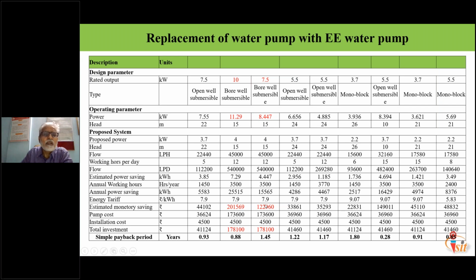For the proposed power, we did a computer simulation using available software with Grundfos. For this particular application, considering the head and discharge, a 4 kilowatt pump is suitable. Head is 15 meters, and the required flow is 45,000 LPH for both cases, with both pumps working 12 hours.